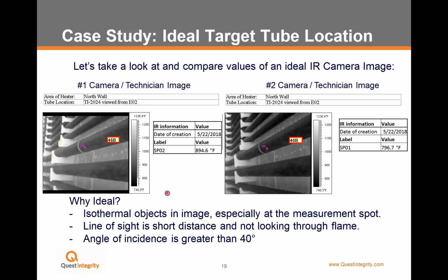And the angle of incidence. We didn't talk about it much earlier, but if you're watching TV, you kind of want to be sitting in front of the TV. You don't really hear parents complaining, my kid is always sitting at the side of the TV, right? The reason is they are always sitting in front of the TV, because just like light, infrared is best when it's seen in a perpendicular pattern. Whenever you get to a 40-degree angle or less, that starts affecting your temperature reading, and emissivity for those surfaces will need to change in order to apply a proper correction.